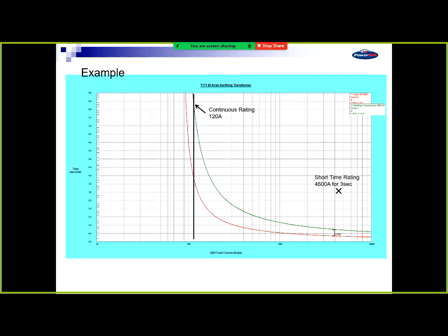So if you just went through the maths with that current, you'd find that that's the current difference. You'll see that the green curve sits above the red curve all the way through there. That's the advantage of picking the same pickup as they did and just changing your time multiplier, which just shifts the whole curve up. It's going to be a bit slower, but it grades over top of all the protection downstream. It protects the local supply transformer because it's rated for 4,600 amps for 3 seconds. So you're going to clear a fault at that level in about 0.8 of a second. So we're well below the short time rating of the earthing transformer. So our transformer's happy. Their protection should operate. If it doesn't, we'll trip out.